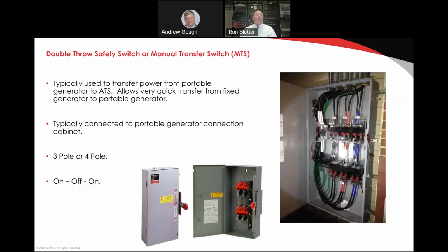So one of the things that I talked about in the single line was the manual transfer switch. This is an example of a manual transfer switch. Really, it's an on, off, on switch. As you can see, the gray box here in the center has the on, off, on capability. So one of the on positions would be the fixed generator, and then you would connect the portable generator to the other on position, and you would simply switch between the two to perform a maintenance activity. So this is a typical piece of equipment used in telecom facilities to facilitate the maintenance and uptime of the facility, even if you take out your fixed generator.